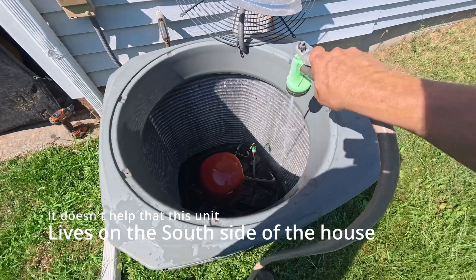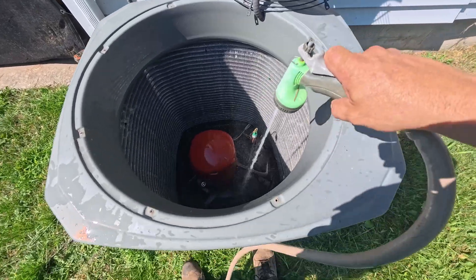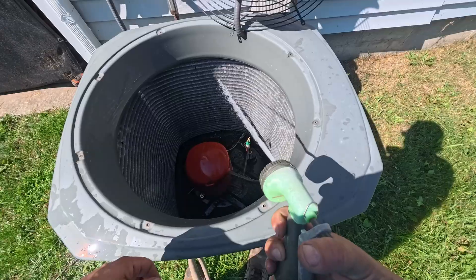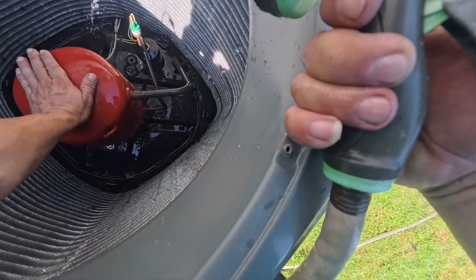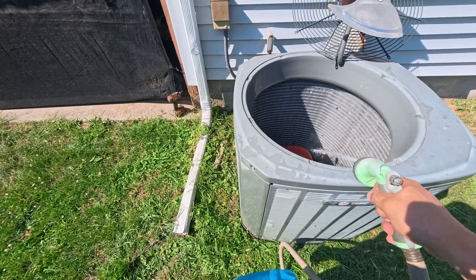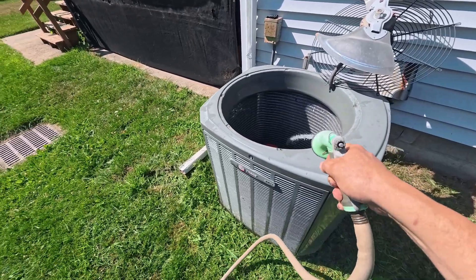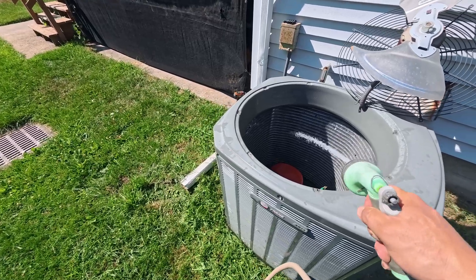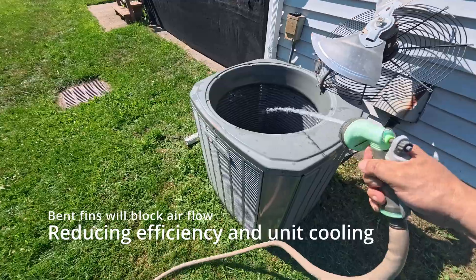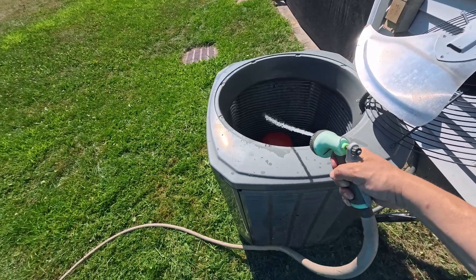It's been exceptionally hot here - actually most of the week. I probably should have measured the temperature of the compressor. She's warm but I can touch it. You don't ever want to use a pressure washer on these coils - you'll bend the fins all up. Regular hose pressure is fine, just keep an eye on what you're doing. Smash all the fins over and you're not going to get any airflow to it.